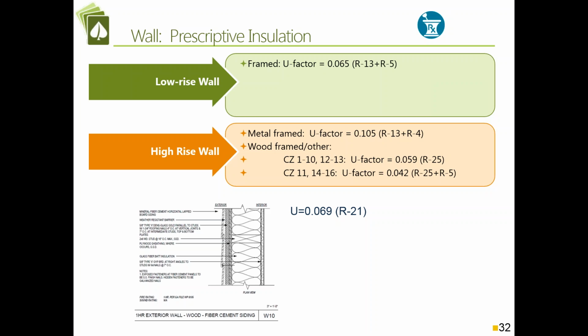The low-rise walls are at a 0.065 U factor, equivalent to an R13 wall with continuous R5 exterior insulation, which is not all that common. If you have a 2x6 framed wall these days with R21, that'll be at 0.069 - the detail on the bottom left. An R21 2x6 wall is at 0.069, which we'd normally think of as a great wall, but it's not even meeting the prescriptive requirement any longer.